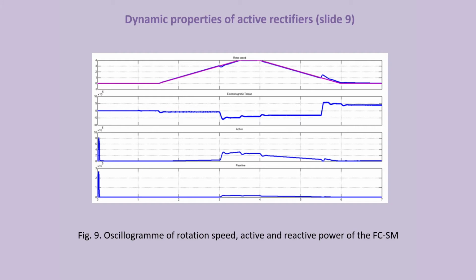As is seen from the speed diagram, the static control system after the load surge reacts to dynamic speed slumps and monitors the signal by the speed. The diagram of consumed active power is determined by the motor speed and torque. Reactive power is minimal and provides the power factor very close to 1. The system is also able to generate reactive power. The system has four control channels: by the input reactive current of the active inverter, by the set output voltage of the active rectifier, by frequency and the pulse ratio of the inverter voltage.